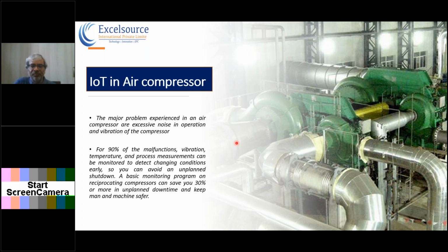So here also, if it is a water-cooled air compressor, we need to install temperature transmitters on both sides of the condensers. On the air side also we need to install temperature transmitters. We can use oil temperature sensors to utilize the hot oil, using its heat to generate hot water, which can be done by modifying existing air compressors. Nowadays, new air compressors come with heat recovery from the hot oil that is used for lubrication of the element.